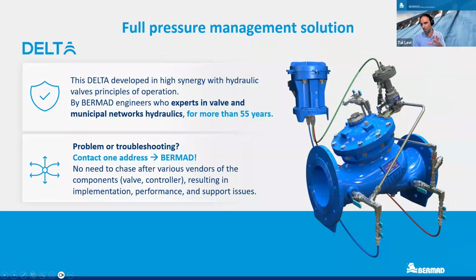And this PRV is not a very simple product. It's not like a 4-20 motorized pilot controlling a butterfly valve. It has a pilot, it has a restriction, it has a control chamber, it has a filter, and it works based on differential pressure across the valve and many other factors. And we took all those things into the algorithm of the unit, which makes the pressure result accurate, stable, and the operation of the unit efficient without draining the battery, and this is critical.